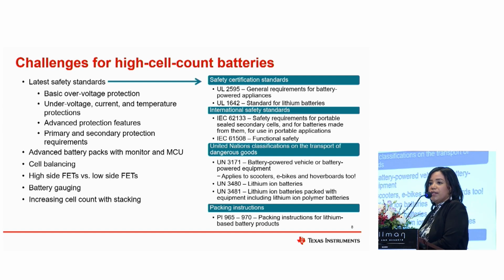And another important consideration: some of the monitors and protectors we have go, let's say, up to 20S. So if you're working in a system that goes to extremely high voltage, such as an automotive or ESS system that goes all the way to 1,000 volts to 1,500 volts, you need to be able to stack them together. So how to consider stacking your solution to create those high voltages is also pretty critical. I'm going to go over in a little more detail some of the basic terminology, as well as the system considerations you need to consider when designing a BMS solution.